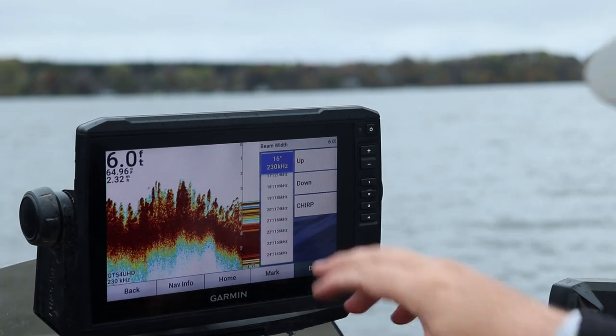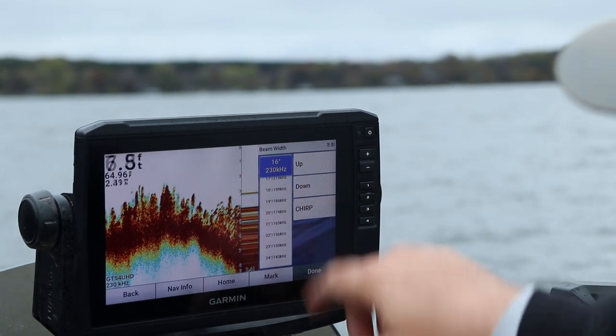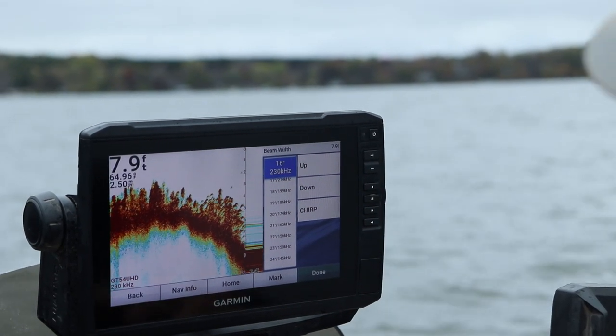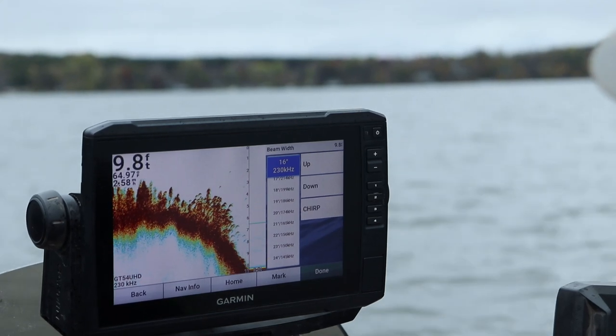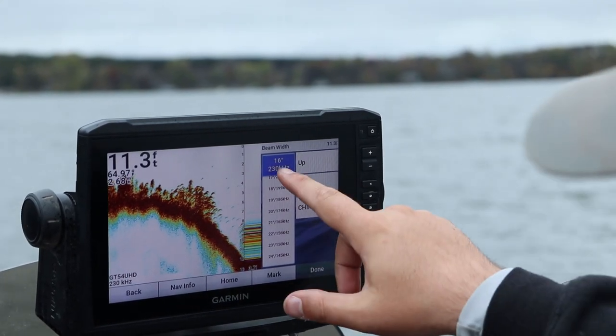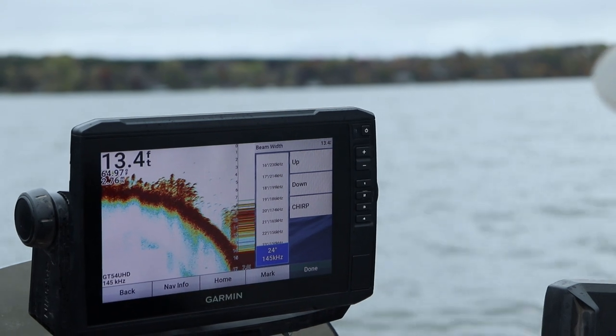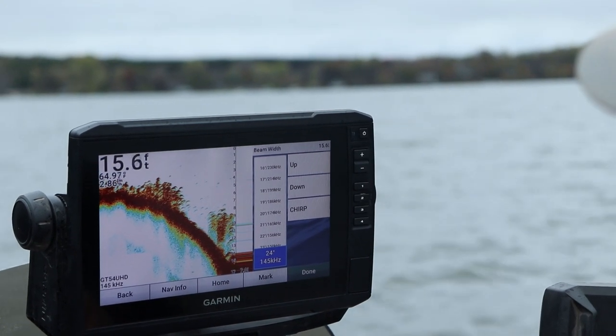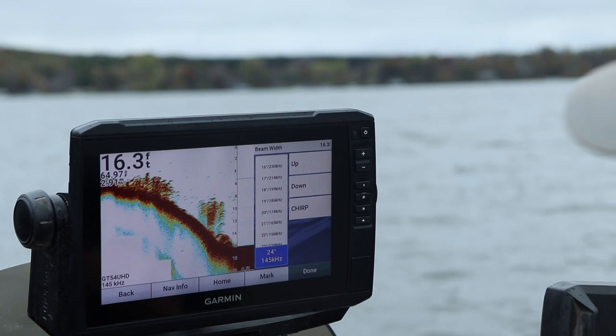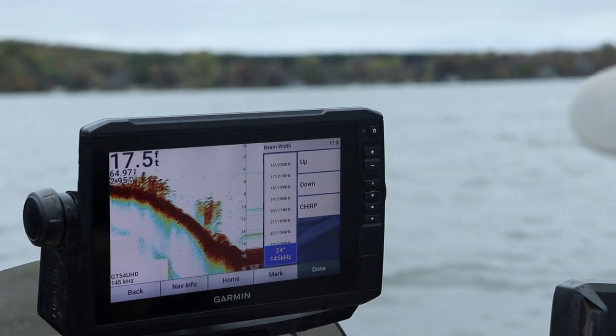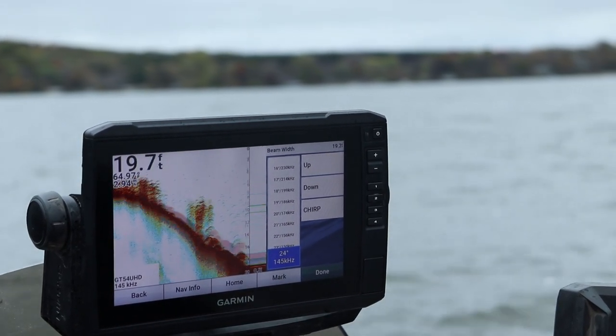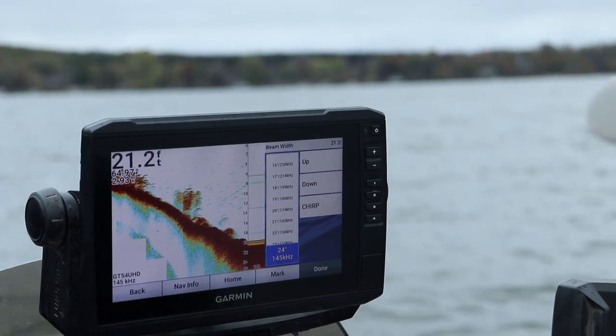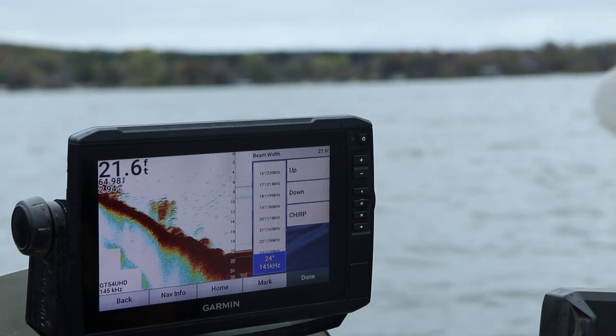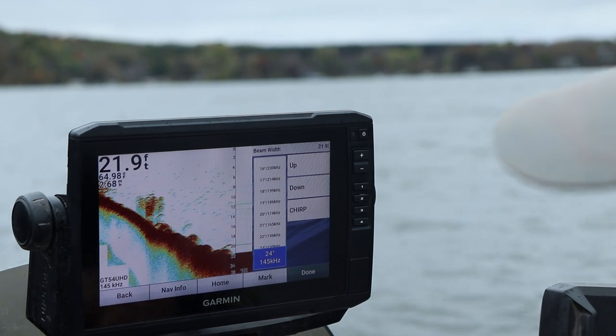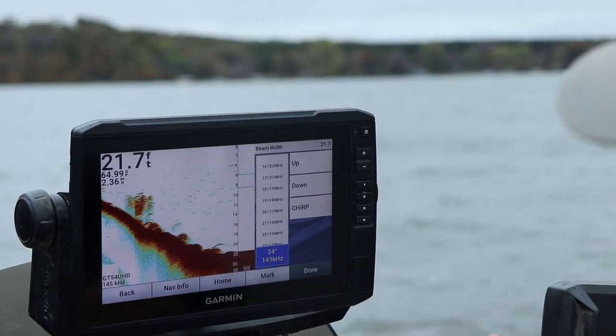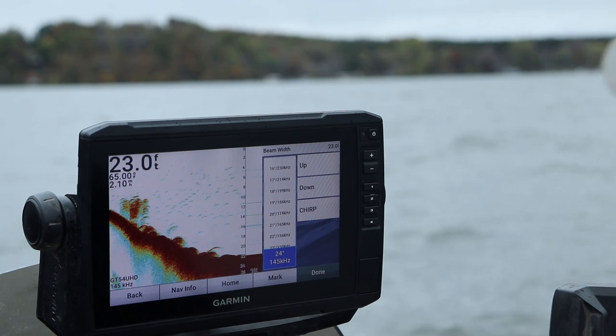As you go up in degree, you get a smaller cone angle with a higher frequency. So 230 kilohertz is a 16 degree cone angle, very narrow. But if I go down to 24 degrees, that's 145 kilohertz, a smaller kilohertz number but a wider cone angle. Let me reinstate that: the lower the kilohertz number, the wider the cone angle; the higher the kilohertz, the narrower the cone angle.